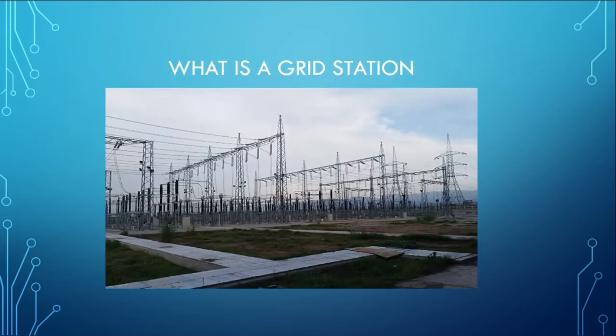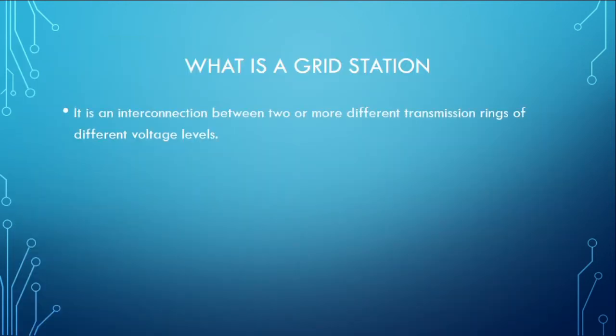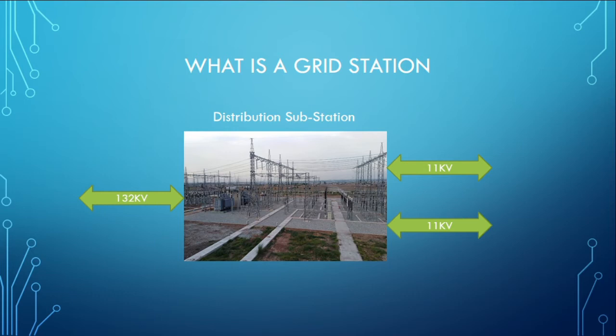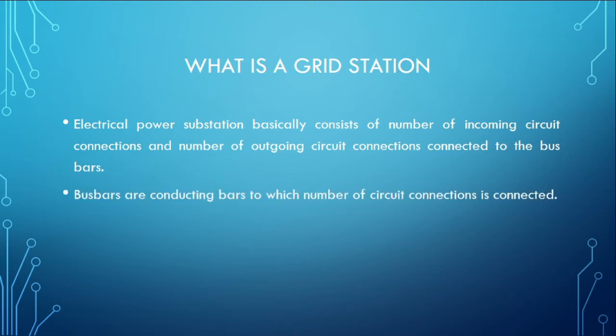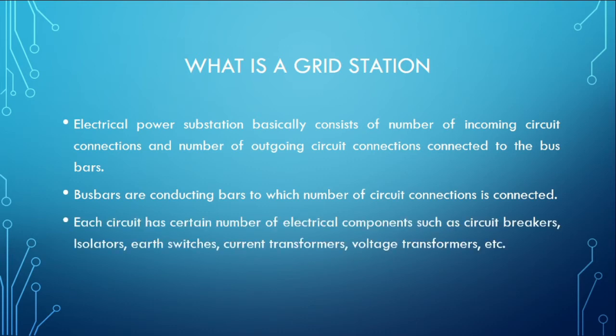What is a grid station? It is an interconnection between two or more different transmission rings of different voltage levels. Our transmission substation has a very high voltage transmission line entering the grid station and two high voltage transmission lines leaving it. The bi-directional arrows show that power can flow in either direction depending upon the situation. An electrical power substation basically consists of a number of incoming and outgoing circuit connections connected to bus bars — conductive bars to which different circuit connections are made. Each circuit has certain electrical components such as circuit breakers, isolators, earth switches, current transformers, and voltage transformers.